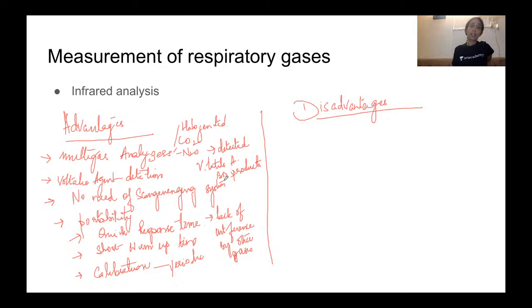So how it detects is, when there is a breakdown product of the volatile anesthetic, these infrared analyzers detect it, even if, suppose, there is a breakdown product of desflurane. This breakdown of these products occurs only when carbon dioxide concentration in the carbon dioxide absorbers is very high and they are desiccated, basically dry. An exothermic reaction is occurring, which is very rare. That is only when faulty carbon dioxide absorbents are used, but otherwise it does not occur.